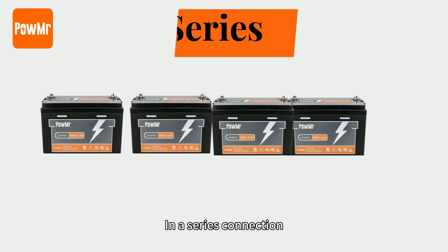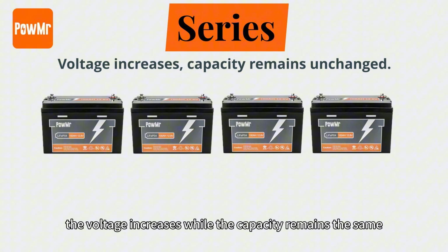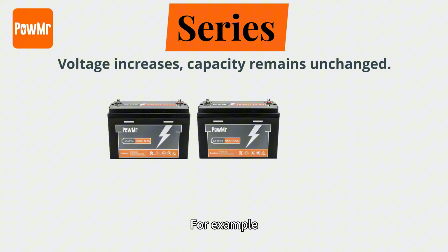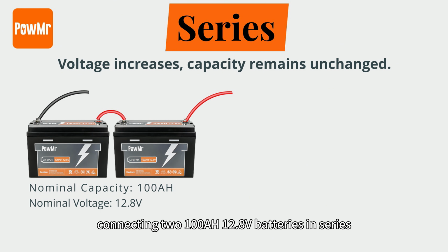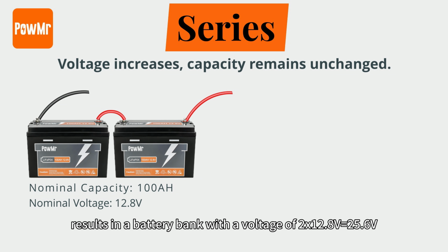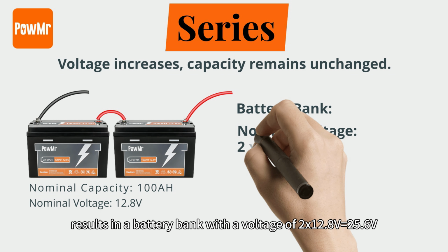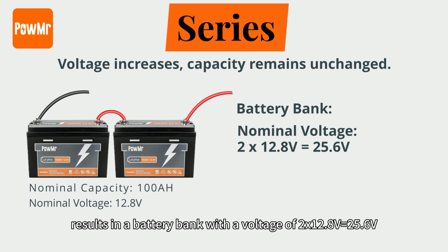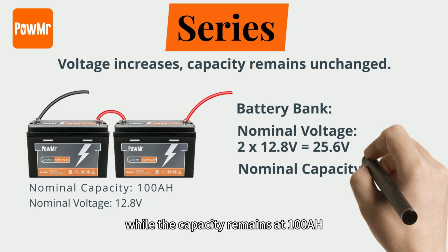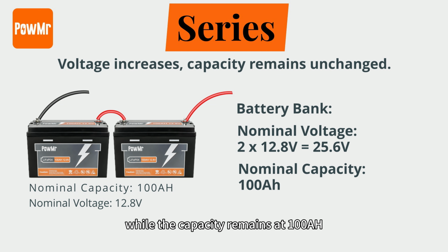In a series connection, the voltage increases while the capacity remains the same. For example, connecting two 100 amp hour 12.8 volt batteries in series results in a battery bank with a voltage of 2 times 12.8 volt equals 25.6 volt, while the capacity remains at 100 amp hour.